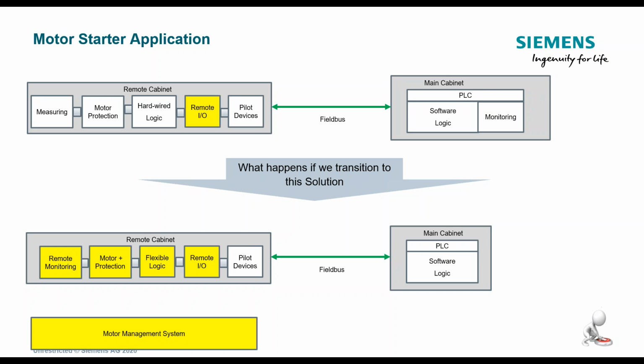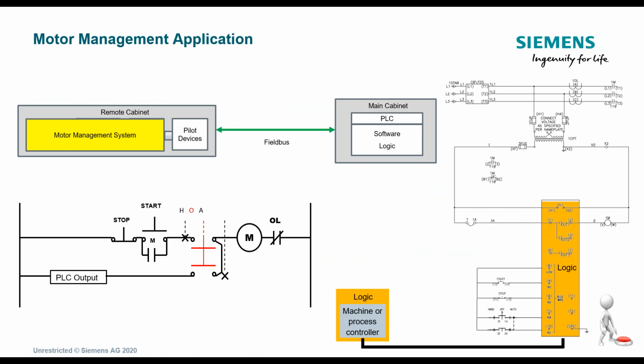Okay, so this box of remote cabinet is where we come in with the motor management system. And this is where Simocode slides in very easily and provides awesome power for your motor control system. So if we introduce a Simocode into that circuit of what we showed earlier of the motor, HOA, and stop and start, here's one thing that we are immediately eliminating. We don't need that auxiliary contact saying that the motor's running. This guy can go away, because the Simocode will be automatically monitoring current and seeing that it's going. And then if you did do a momentary push button or a maintain push button, it's just a checkbox in the Simocode, and it will eliminate using that auxiliary contact.